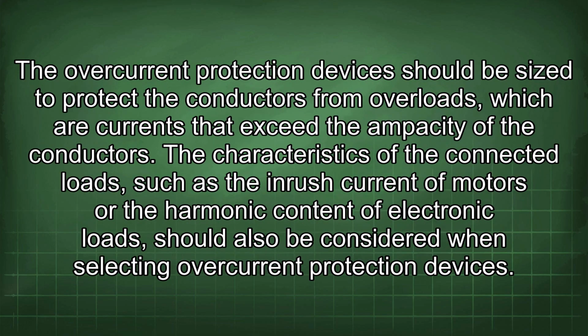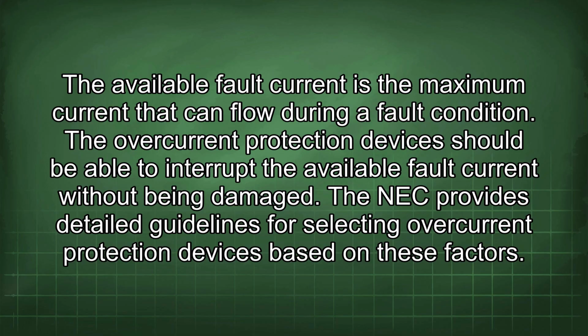The overcurrent protection devices should be sized to protect the conductors from overloads, which are currents that exceed the ampacity of the conductors. The characteristics of the connected loads, such as the inrush current of motors or the harmonic content of electronic loads, should also be considered when selecting overcurrent protection devices. The available fault current is the maximum current that can flow during a fault condition. The overcurrent protection devices should be able to interrupt the available fault current without being damaged. The NEC provides detailed guidelines for selecting overcurrent protection devices based on these factors.